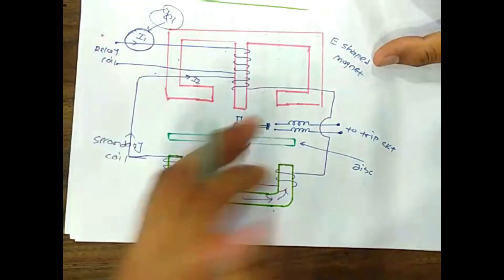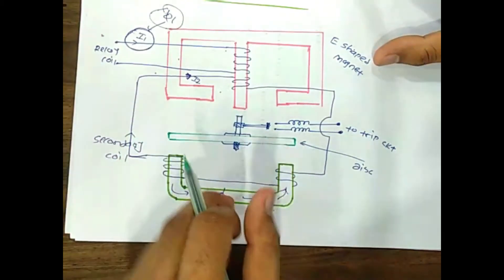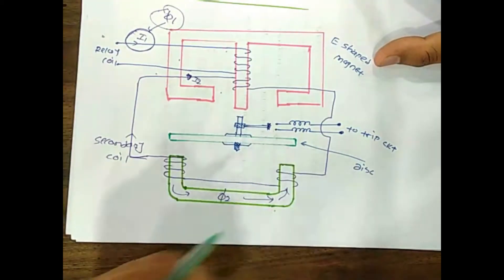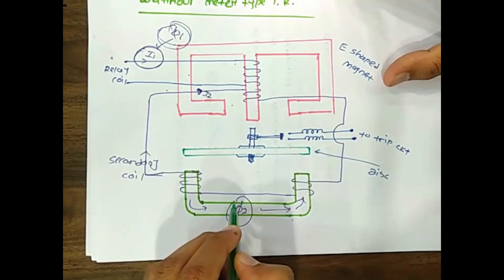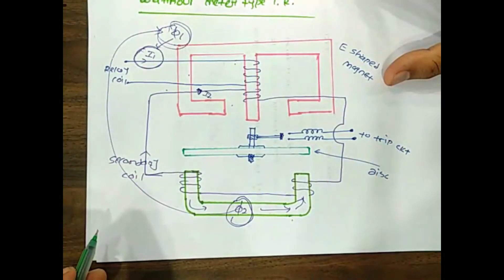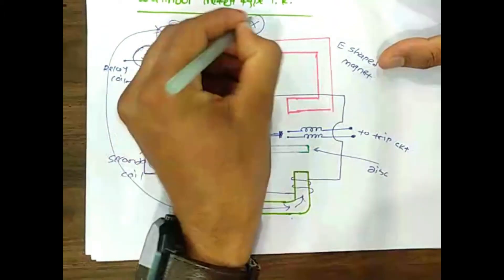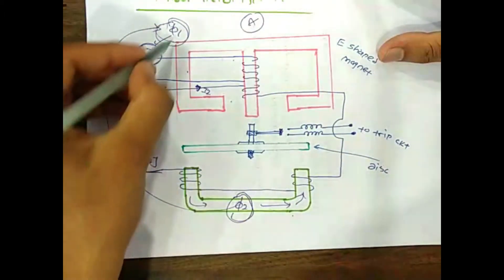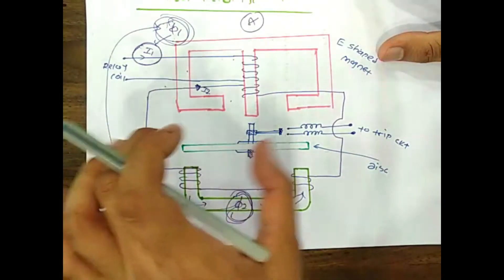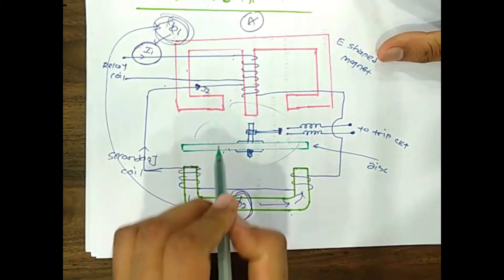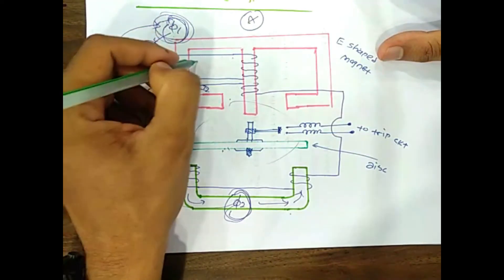Because of i1, flux phi1 is produced, and due to this flux, an EMF is induced in the secondary. This drives the current i2 through the secondary. Due to current i2, flux phi2 gets produced in the lower magnet, and this flux lags behind the main flux phi1 by some angle alpha.